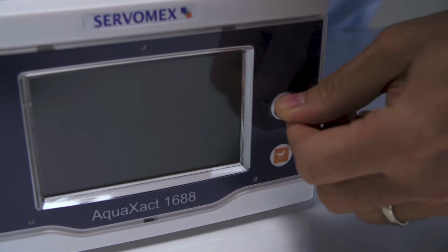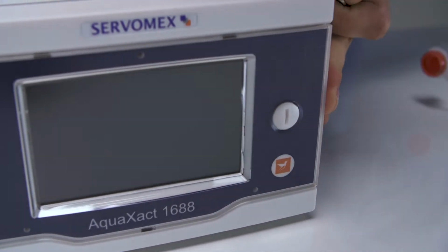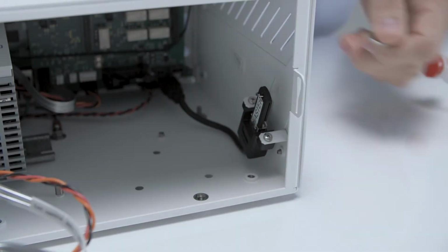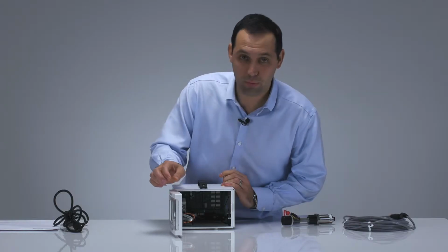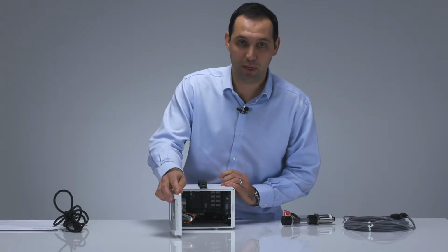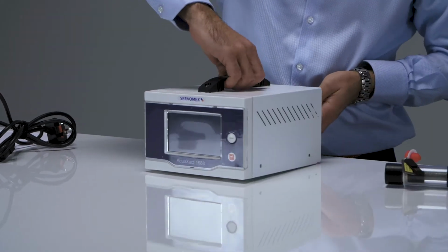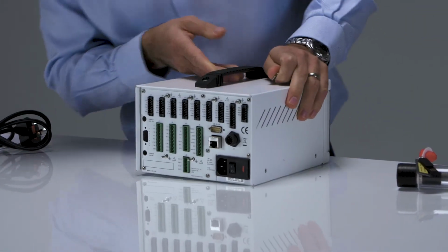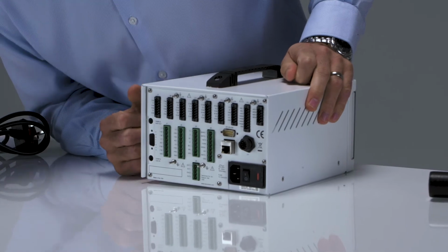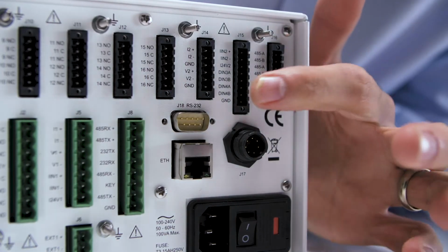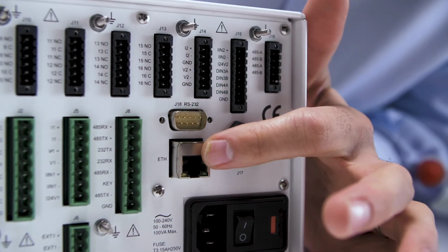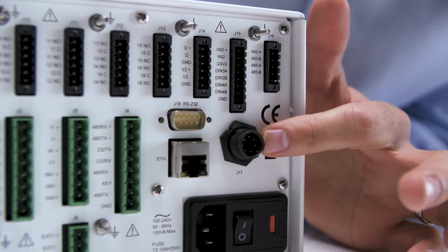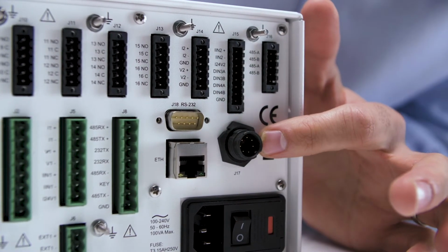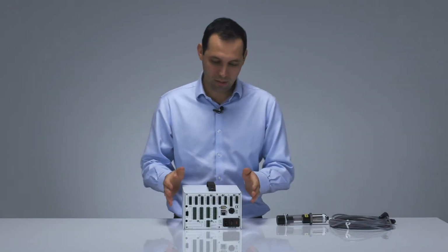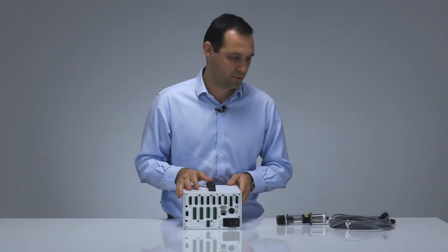On the front, you have an access point here, openable with just a coin, and you can see you have a USB slot here for updating any calibration data when you replace the sensor tip. On the rear of the analyzer, you have numerous relays, digital inputs, digital outputs, Profibus connection, RS-232, Ethernet, RS-485, and all importantly, the AquaXact 1688 7-pin connector. Now we can connect the AquaXact controller to the AquaXact sensor. So we take our connector.